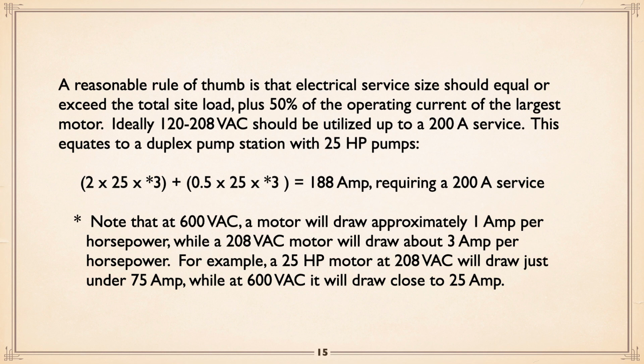As I always say, why do we use 600 volt and why is it so important? Because at 600 volt, a motor will draw approximately 1 amp per horsepower. In other words, if you have a 40 horse motor, if you look up the manufacturer's information, it'll be very close to 40 amp at 600 volt. Others are proportional. And if I can do this correctly in the back of my mind, realize as voltage goes up, current goes down. As voltage goes down, current goes up. 600 volt, 1 amp per horsepower.